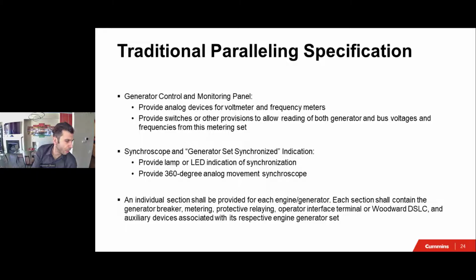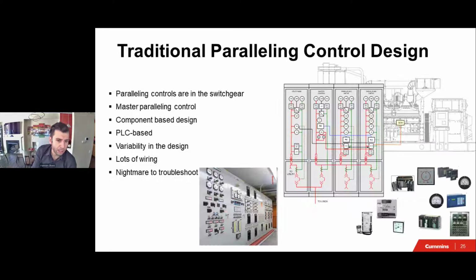So traditional paralleling control and design starts out with the paralleling controls in the switchgear. There is a master level controller. It's a component-based design, and it's PLC-based. So the design is PLC-based with lots of wiring, and it's what we call a nightmare to troubleshoot and design.